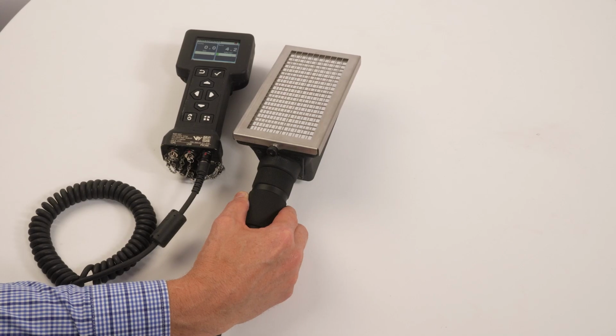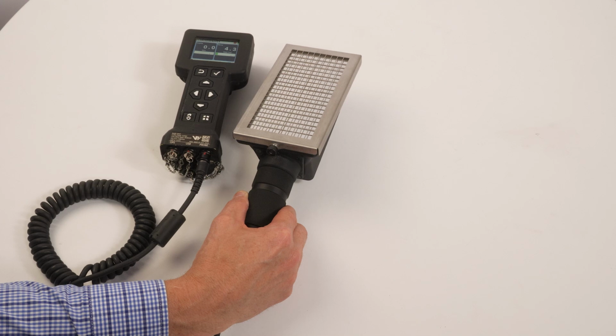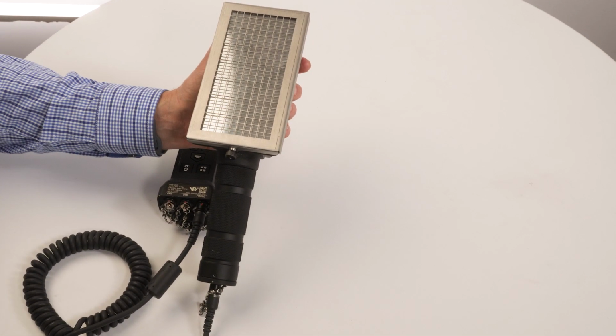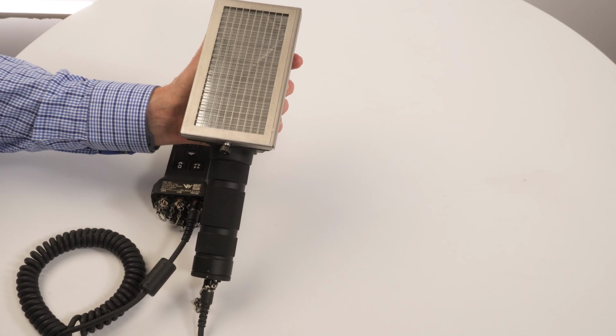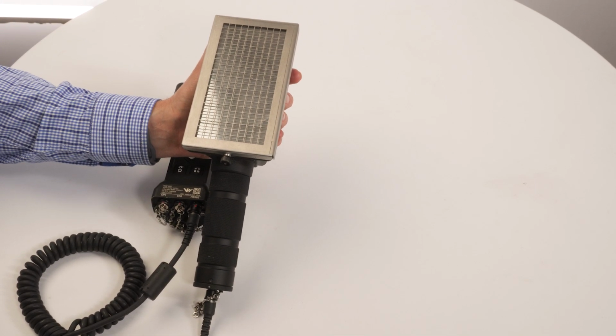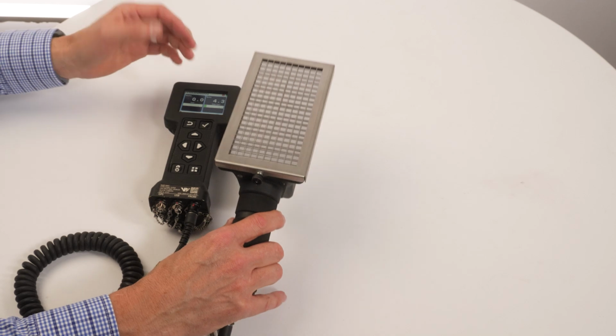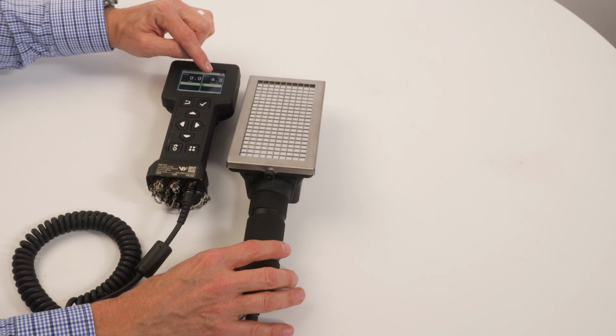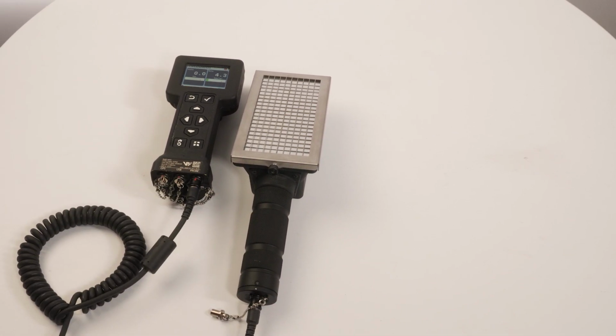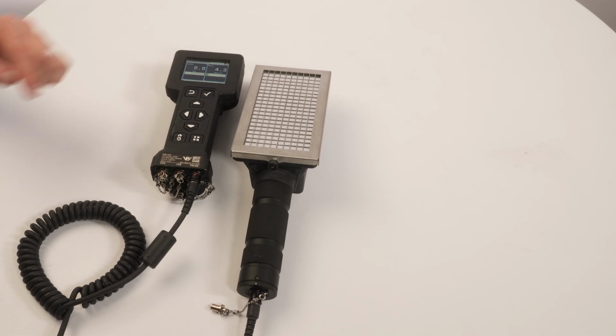Occasionally, the alpha-beta probe's mylar window can get damaged and cause a light leak. A light leak is manifested by an abnormal increase in either the alpha or beta readings when the probe is in operation. So let's do a light leak check. Turn the face of the alpha-beta probe towards a source of light like overhead lights or a window. If there is a light leak, the alpha or beta counts will increase significantly.